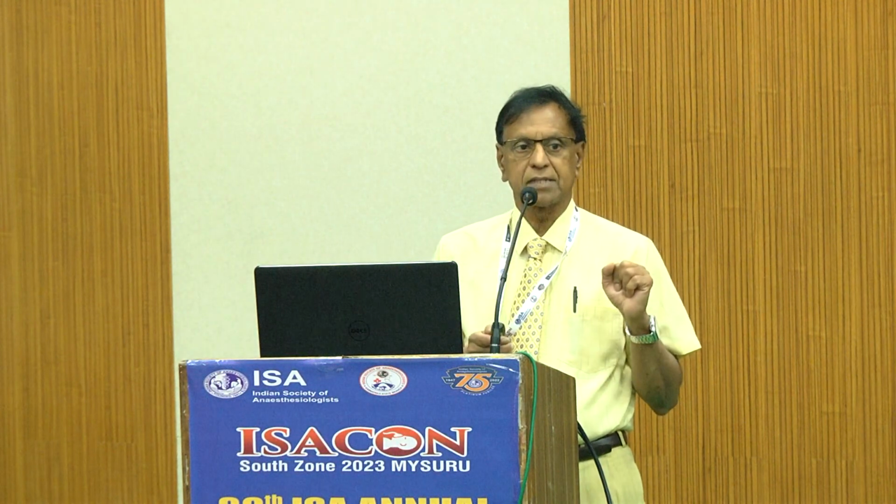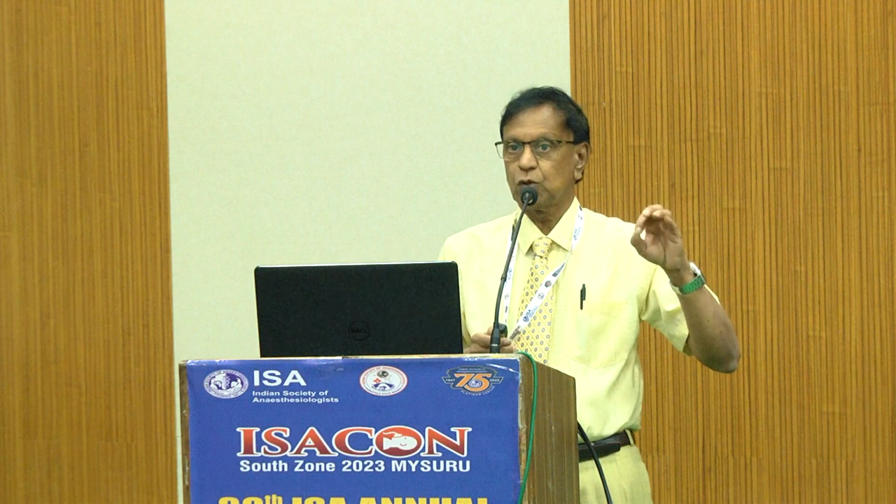Now, just a little bit of physics: you have to understand that CO2 is a polyatomic gas and it absorbs infrared light at 4.3 microns. So we use infrared technology to measure CO2 in our clinical practice. Water vapor, H2O, and nitrous oxide are also polyatomic, so they also absorb infrared light, but at a slightly different frequency.